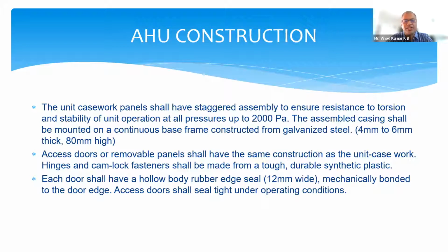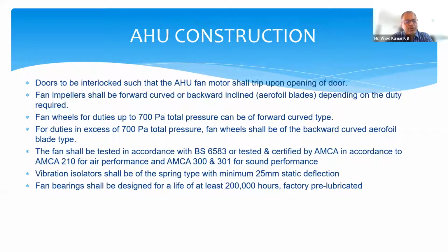At the same time, it will also take in air from outside if it's kept on the terrace or in a place where it is very dirty. So what is important is that the doors, which we call access doors or removable panels, have a rubberized seal so that it's airtight when closed and under operating conditions. Now, the door is important, but when the AHU is running, the door should not be openable. If you open the door by mistake when the AHU is running, it's going to be a safety issue for the maintenance person.